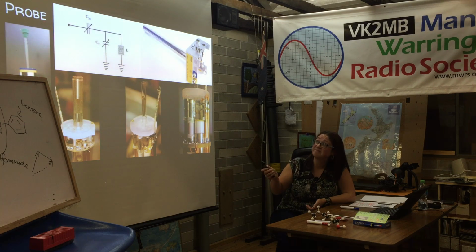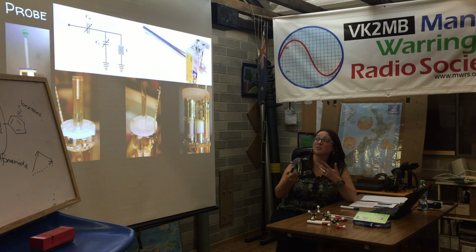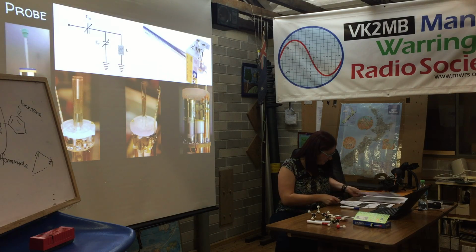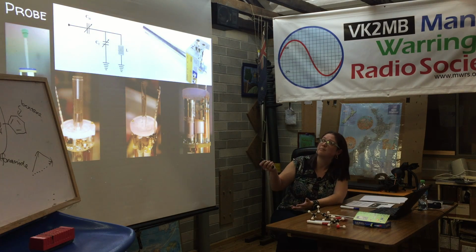The probe is a tank circuit. We have two adjustable capacitances, matching and tuning. So this comes back to what you were saying before. We have to have the circuit on resonance and have to match it to 50 ohms of the coax cables. So when we do tuning and matching, we're adjusting this so that this oscillator is on resonance and it accumulates energy.